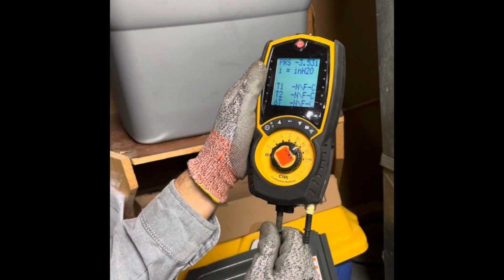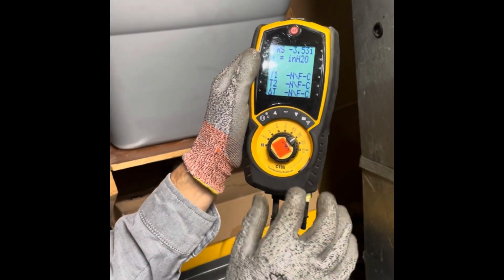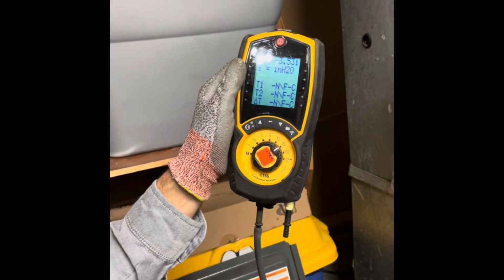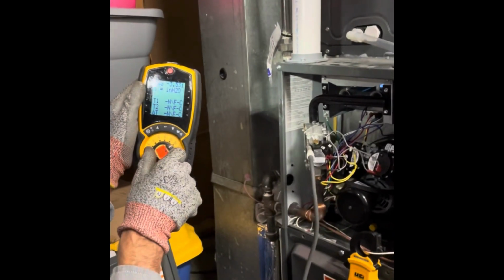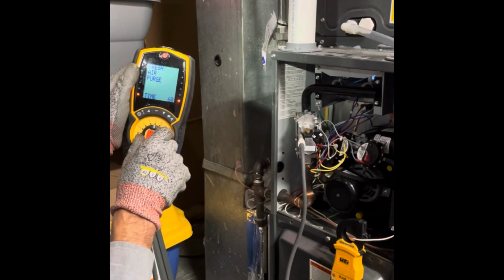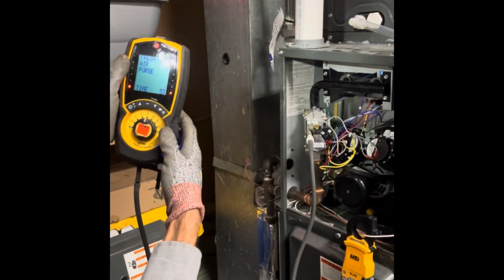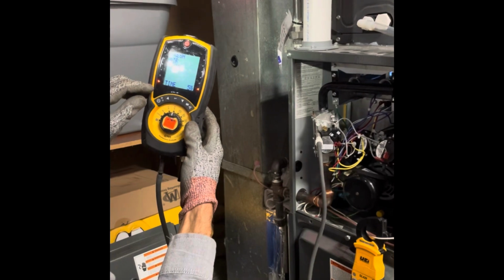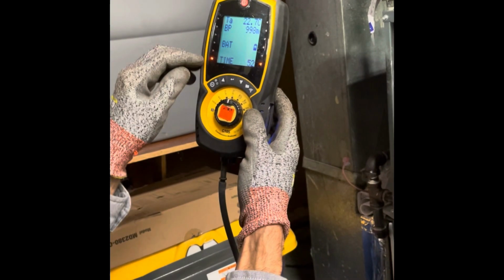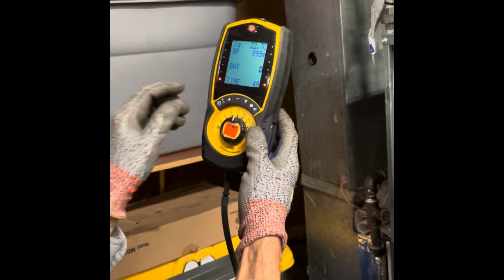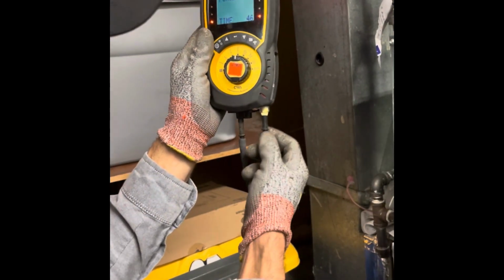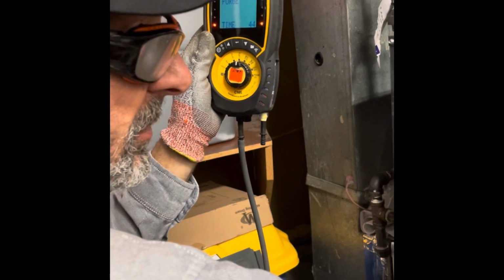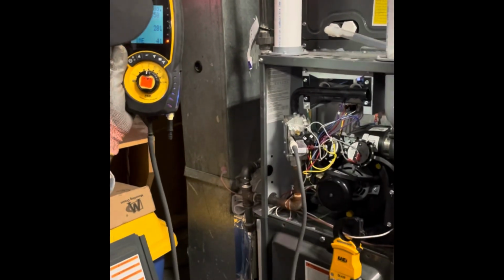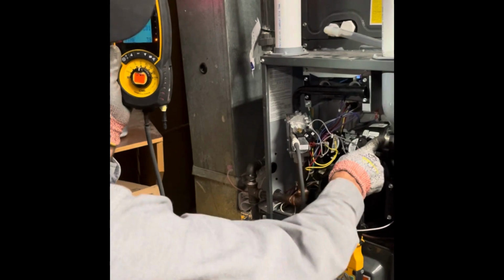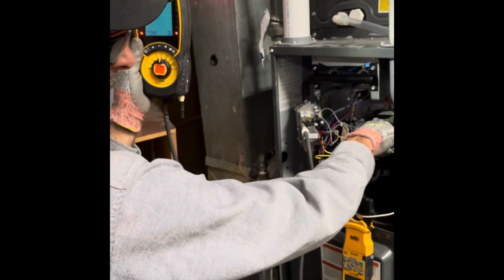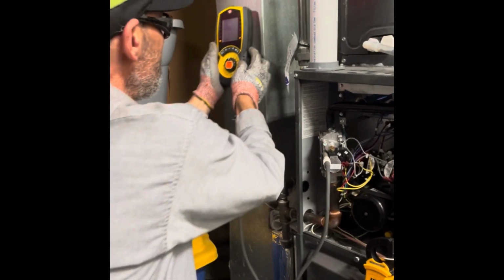So 3.52. So the next step I'm going to do is a carbon monoxide test in this exhaust stream. 200 parts per million. I don't want to see over that number. Being a 1-year-old furnace, I don't think we're going to get close to that. So we've got a fresh air purge of 53 seconds. Once we get down to 0, I will hook up a hose to this probe here, to this nipple sticking out. There's a little rubber plug here. I can check CO here. Whenever I do a CO check, I get the highest reading right at the port here. So we'll let this count down.